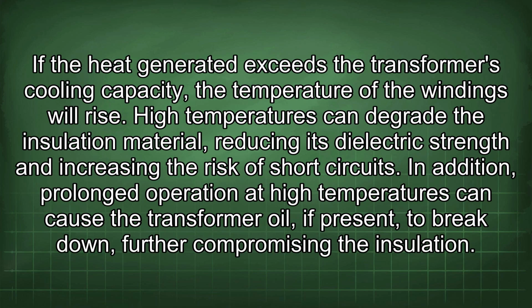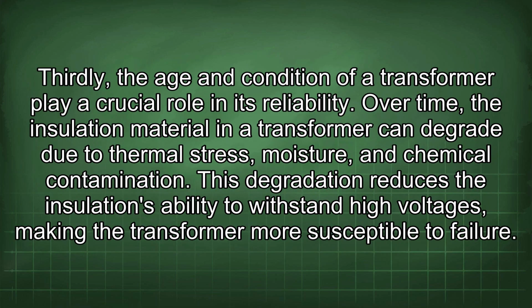If the heat generated exceeds the transformer's cooling capacity, the temperature of the windings will rise. High temperatures can degrade the insulation material, reducing its dielectric strength and increasing the risk of short circuits. In addition, prolonged operation at high temperatures can cause the transformer oil, if present, to break down, further compromising the insulation. Thirdly, the age and condition of a transformer play a crucial role in its reliability.